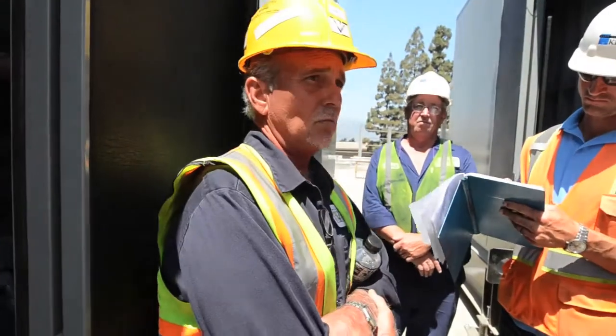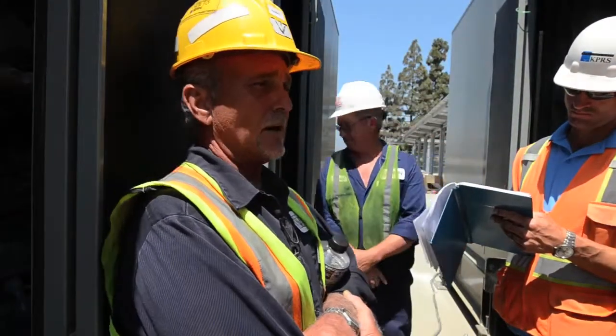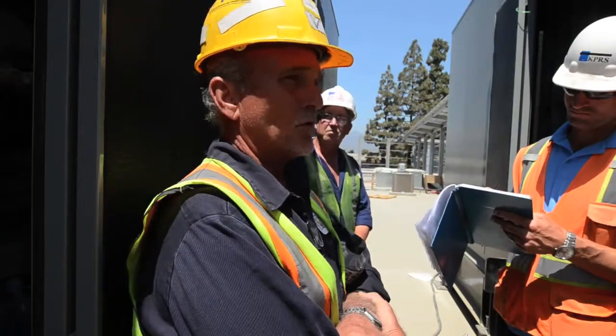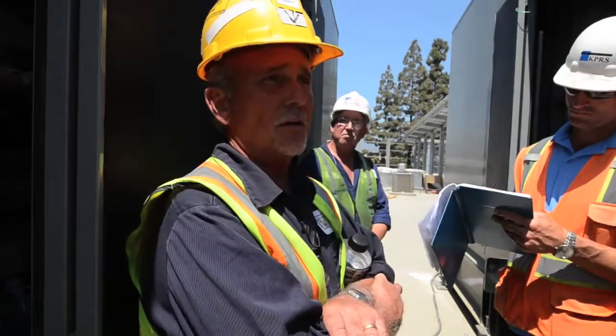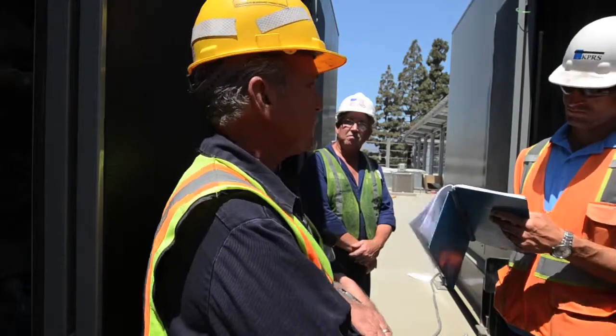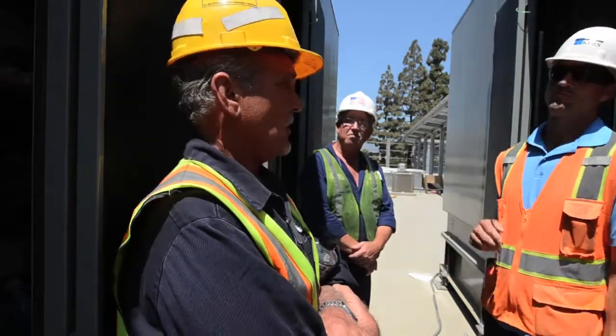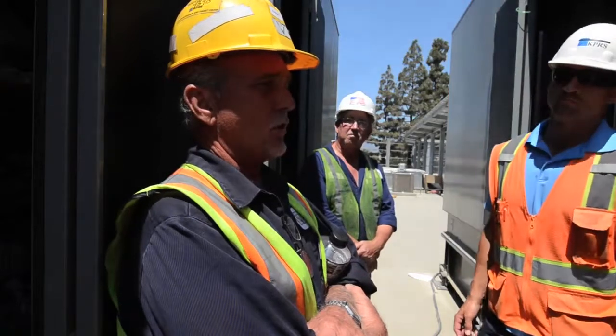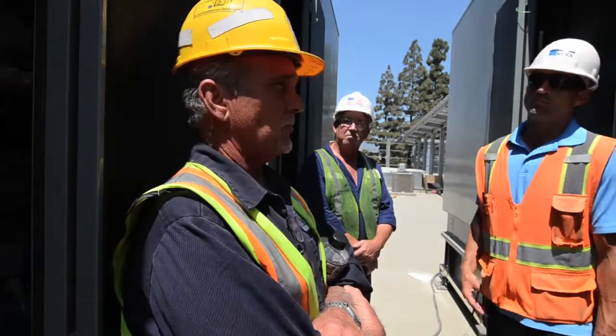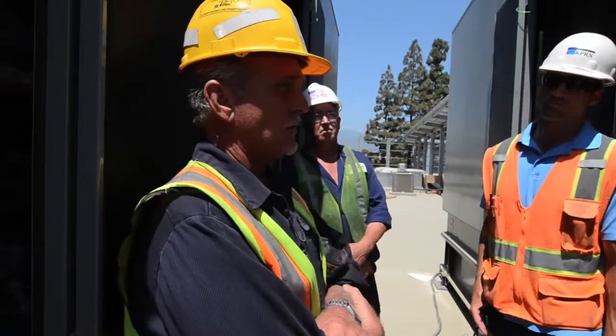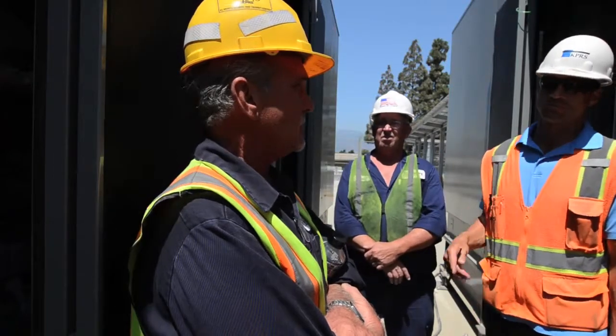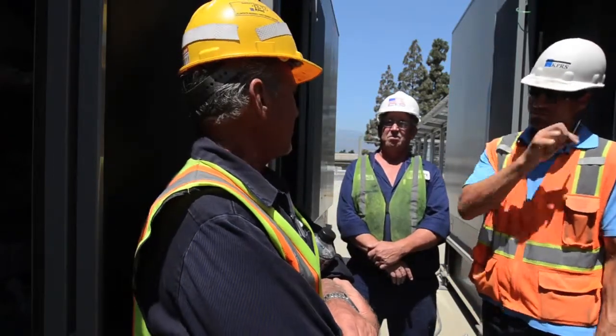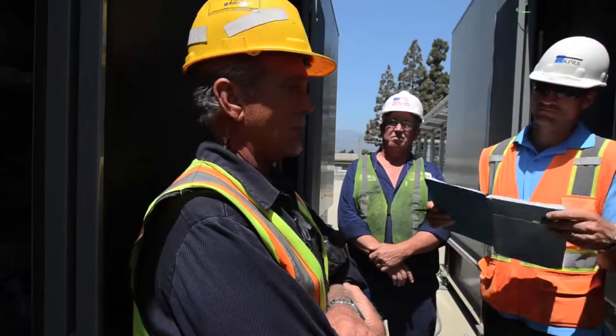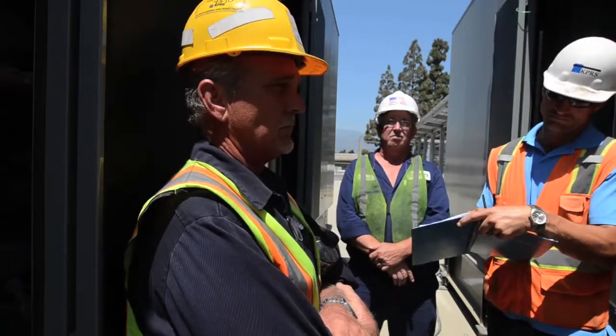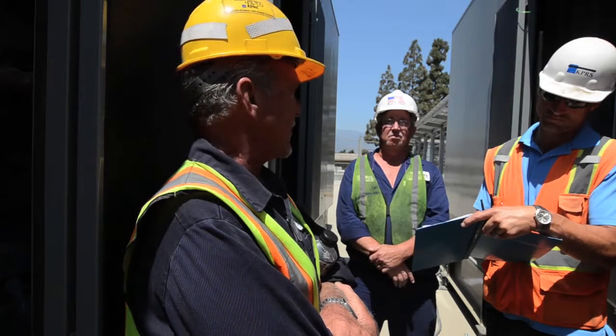Let me tell you the benefit of that: you're helping me out to start with. If you say you've got a low coolant temperature and I need to come address it, I may have parts for a replacement jacket water heater and bring it with me just in case, because I know what you have. Once these units are no longer in warranty and you're paying for repairs, you're going to pay me $120 an hour plus $2.50 a mile to drive up from Temecula to look at it and say, yep, the jacket water heater's bad—I'll go back to the shop and order you one. You just paid me $1,200 to come up and look at it.